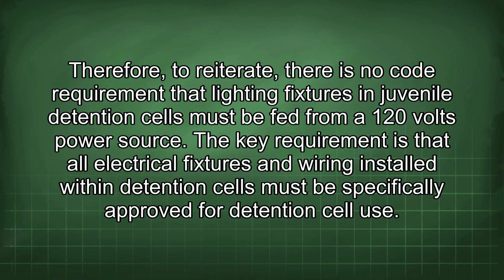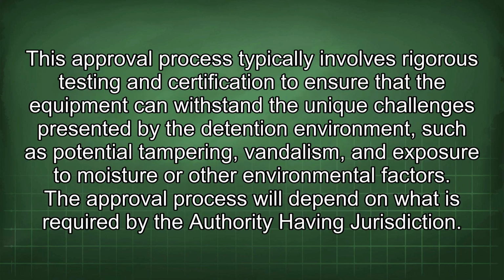The key requirement is that all electrical fixtures and wiring installed within detention cells must be specifically approved for detention cell use. This approval process typically involves rigorous testing and certification to ensure that the equipment can withstand the unique challenges presented by the detention environment, such as potential tampering, vandalism, and exposure to moisture or other environmental factors. The approval process will depend on what is required by the authority having jurisdiction.